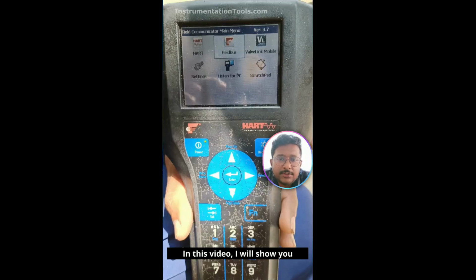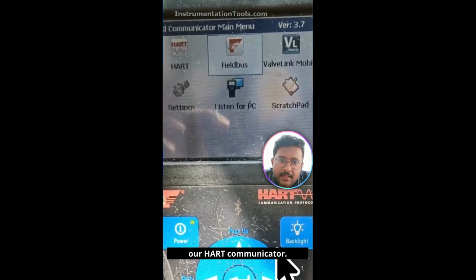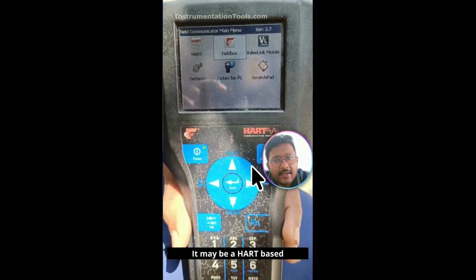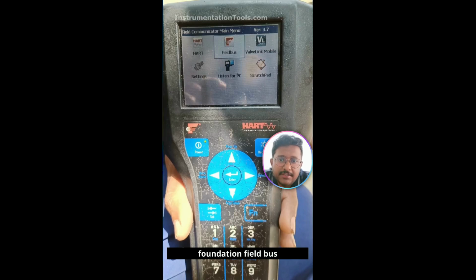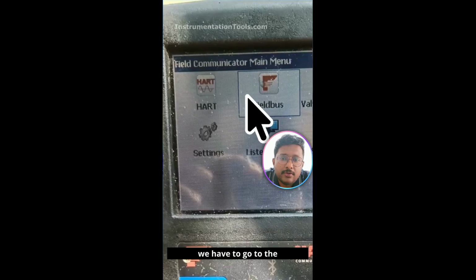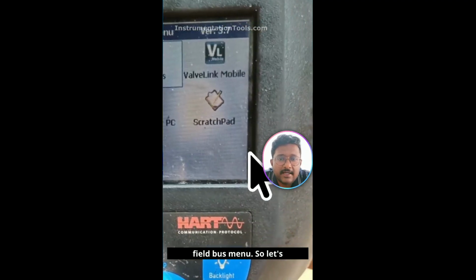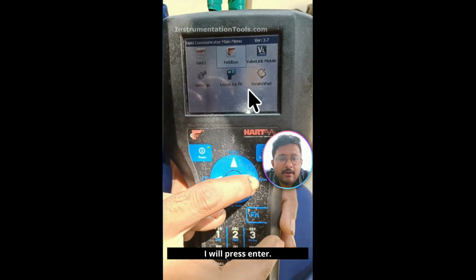In this video, I will show you inside the HART communicator. So this is our HART communicator. Using the HART communicator, you can do the configuration of a device. It may be a HART-based instrument or a foundation fieldbus based instrument. In this case, we are using a foundation fieldbus based device. So we have to go to the fieldbus menu. See, this is the default menu of a HART communicator. As we are using a foundation fieldbus based device, we have to go to the fieldbus menu. So let's see that, and I'll press enter.